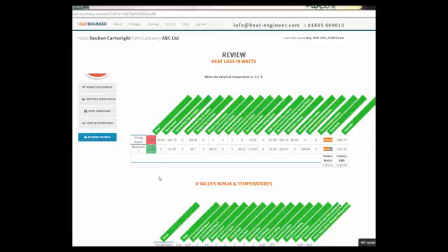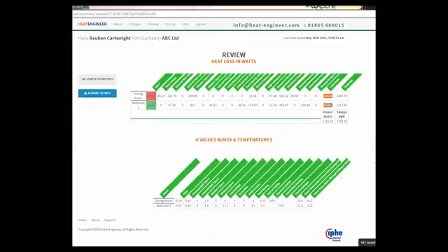And if we had loads of rooms, again there'd be another video showing that. A survey with lots of rooms, it'd be a nice sort of rainbow pattern there, different colours, and the red one will always be the worst performing room, the highest watts per meter squared. We've got the total watts here and the total energy, and if we scroll down, we've also got the U values used, and what temperatures were above and below the room.